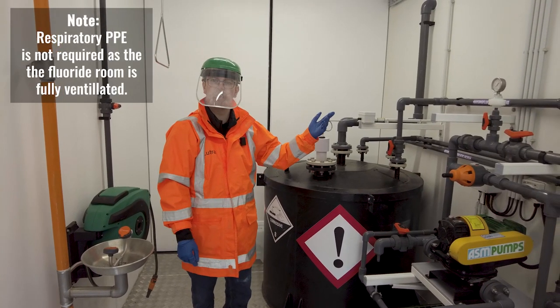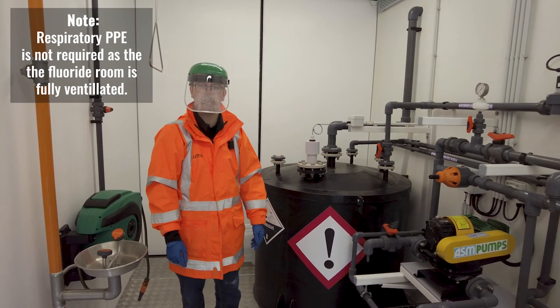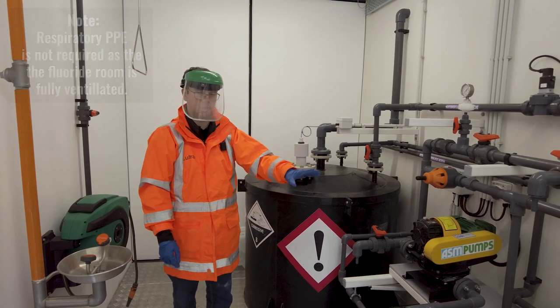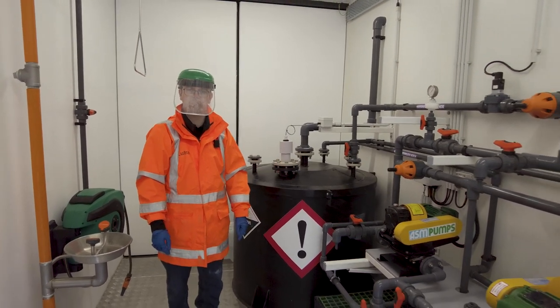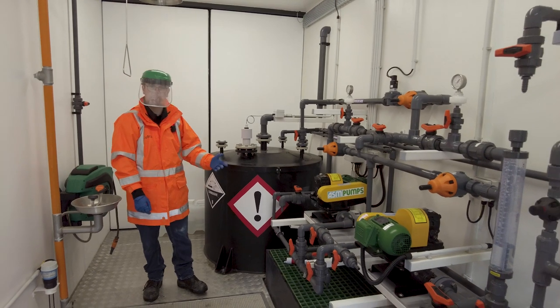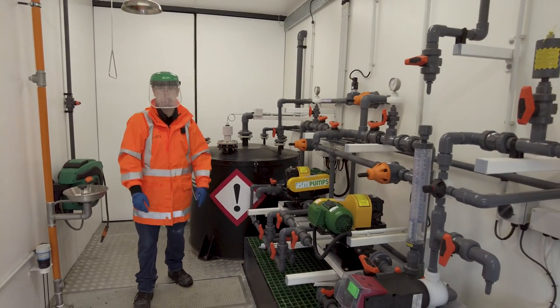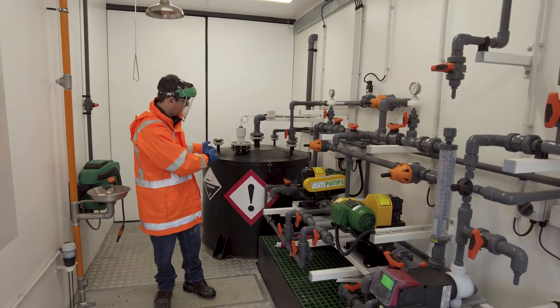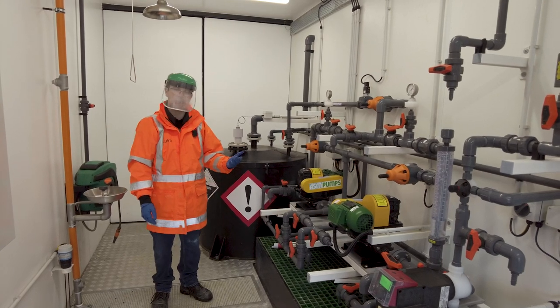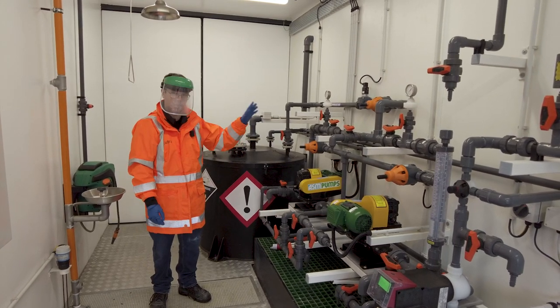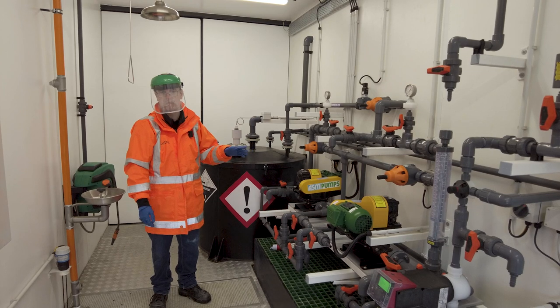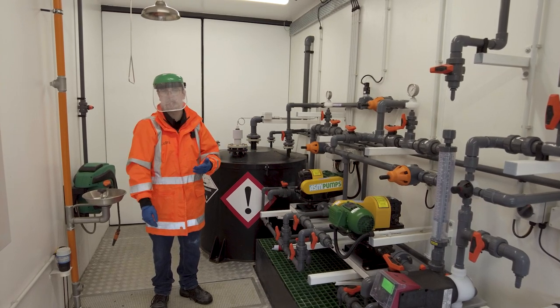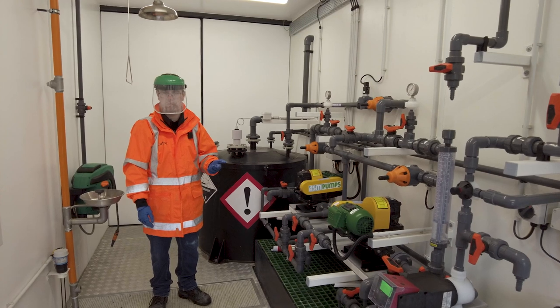From the bulk tank, the fluoride is transferred into this day tank by a series of duty standby transfer pumps. This operation occurs once per day to make sure that only a day's worth of fluoride is present in this tank, and if the system asks to transfer more than once a day, an alarm is tripped indicating that the usage has been higher than it should be.